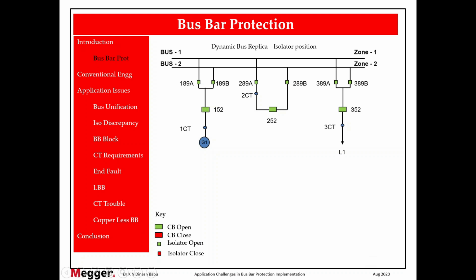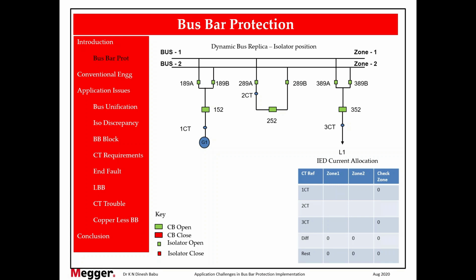So now in this condition, what are the values read by the relay? IED current allocation. So we have to understand this table. This table is very important. We have 2 types of zone concept which we all know, main zone and check zone. So when I write zone 1 here, it is called the main zone. Zone 2 means main zone 2. Check zone means the entire zone. And I have written the CTs here: 1 CT, first bay CT, second bay CT, third bay CT.